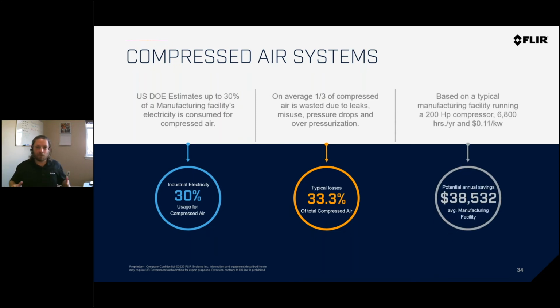So if we put some numbers to this, based on a typical manufacturing facility, a 200 horsepower compressor running 6,800 hours a year. That's basically like 3 shifts a day, 5 days a week, which is going to get you about 6,200 to 6,800 hours in a year at, let's call it, an average of 11 cents per kilowatt. If that leak went the whole year undetected, you would be spending $38,532 in nothing, just in wasted air.